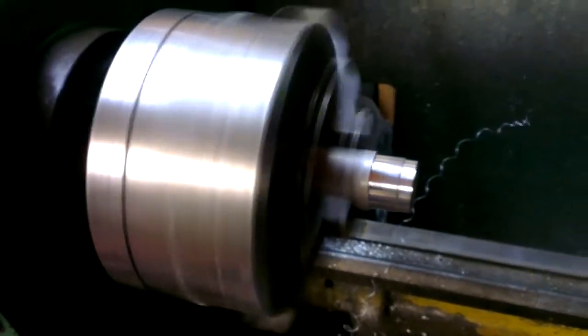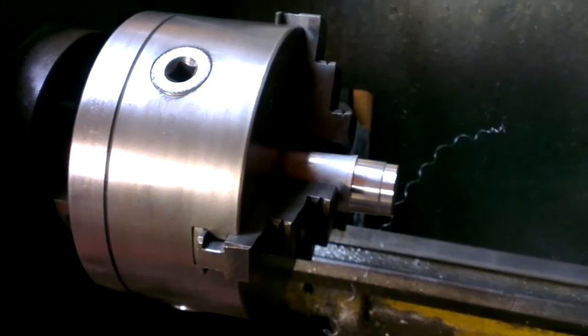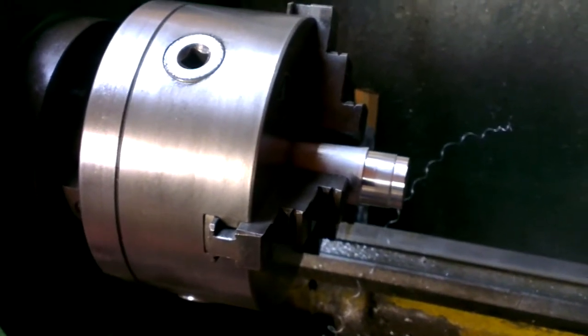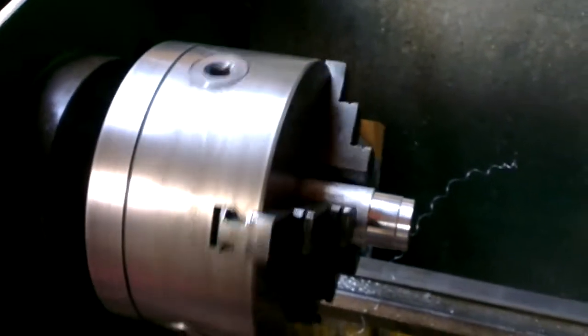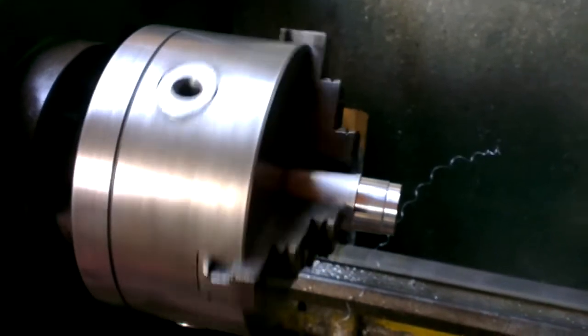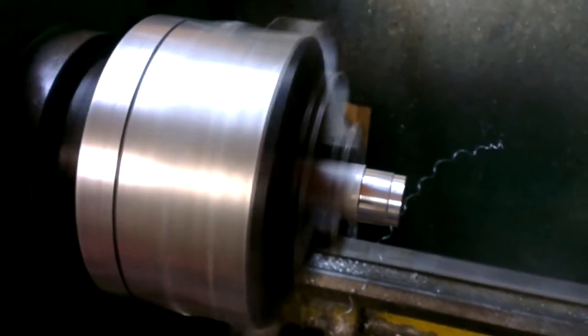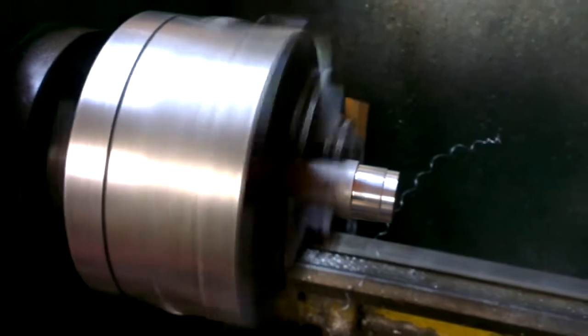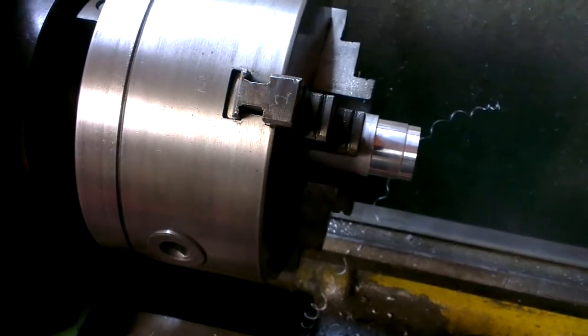That's 30 Hertz. The spindle is obviously turning pretty quick. It's got DC braking enabled as well — flip it into reverse, straight into forward, forward straight to reverse. I think I've got the DC braking set at eight percent. Yeah, should be good.